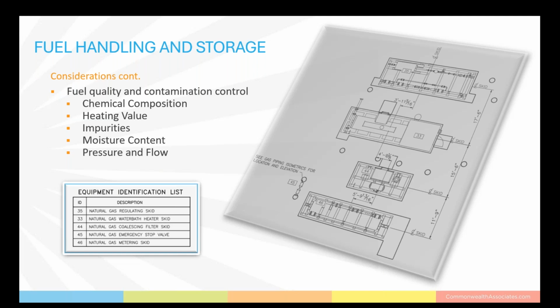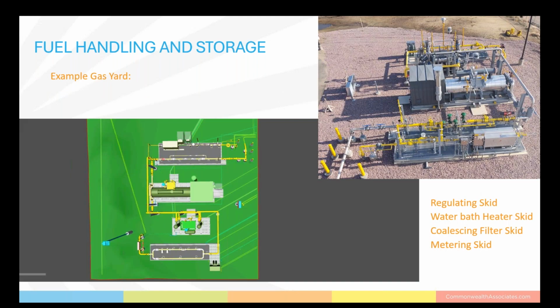Natural gas can have impurities such as sulfur compounds, carbon dioxide, nitrogen, and other trace elements that may need to be removed. The moisture content of natural gas is another factor that influences its quality. Moisture can condense and cause operational issues in pipeline and equipment, so it needs to be controlled within acceptable levels per CHP equipment requirements. Natural gas is transported and distributed under specific pressure and flow conditions. Pressure and flow characteristics include pressure drop and flow rates and can impact the performance and usability of the gas.